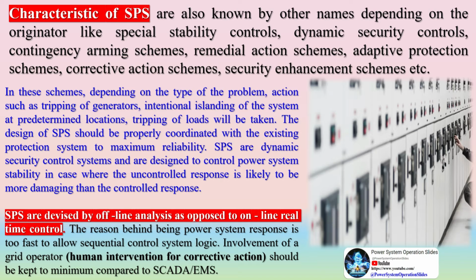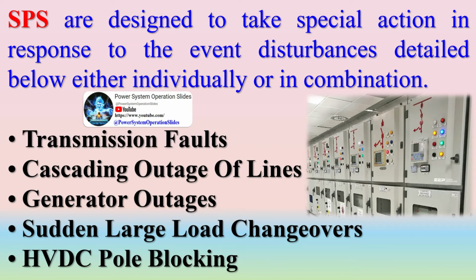SPS initiates corrective actions in mitigating the consequences of abnormal conditions without involving the isolation of faulted elements. SPS are primarily used where the protection is employed on the capability of the power system instead of specific equipment protection. Characteristics of SPS are also known by other names depending on the originator, like special stability controls, dynamic security controls, contingency arming schemes, remedial action schemes, adaptive protection schemes, corrective action schemes, security enhancement schemes, etc. In these schemes, depending on the type of the problem, actions such as tripping of generators, intentional islanding of the system at predetermined locations, and tripping of loads will be taken.